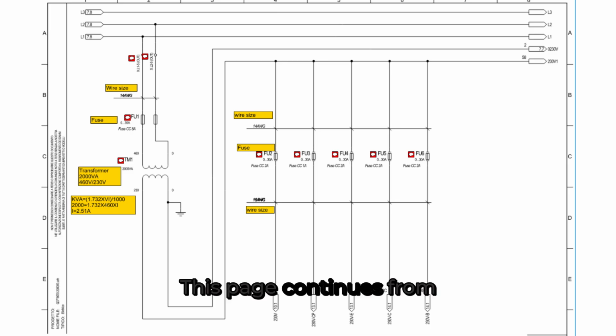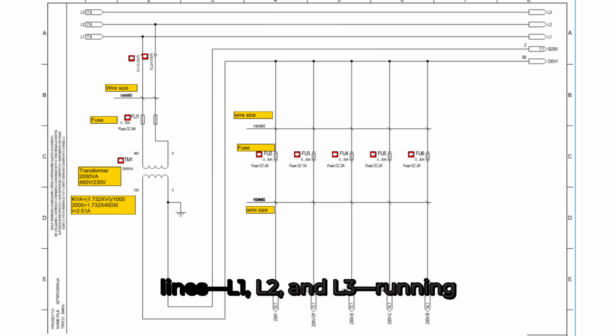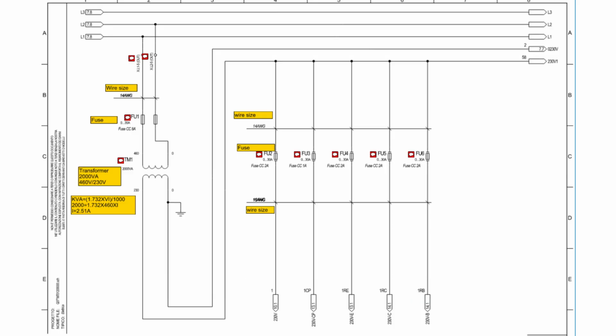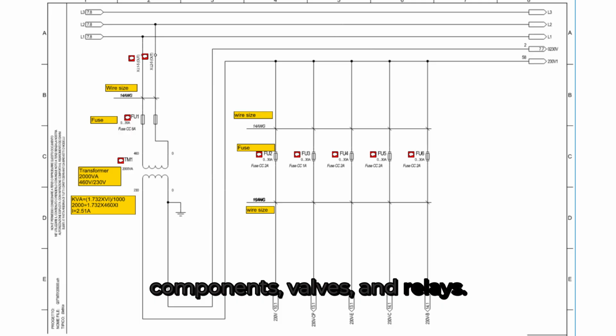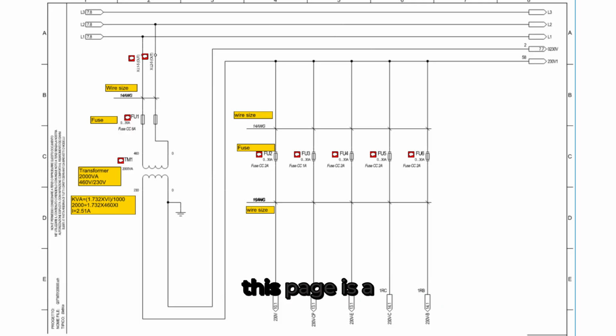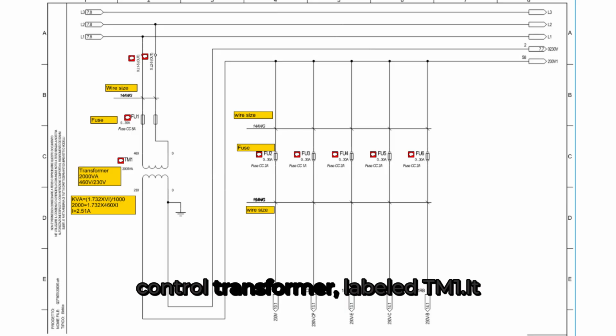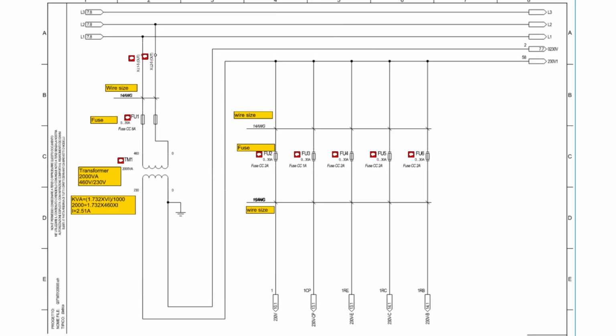This page continues from the same three-phase power lines, L1, L2, and L3, running horizontally across the top. Here, we start tracing the control power circuit, which supplies 230 volts to the unit's control components, valves, and relays. The first component on this page is a control transformer, labeled TM1. It has a primary side rated at 460 volts and a secondary side rated at 230 volts, with a total power rating of 2000 VA.